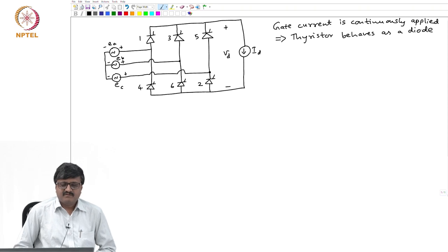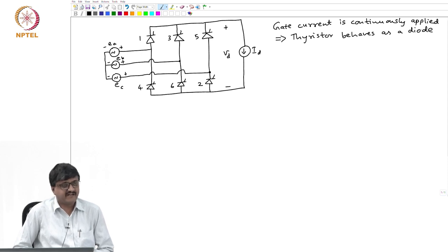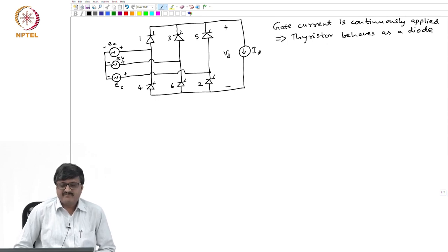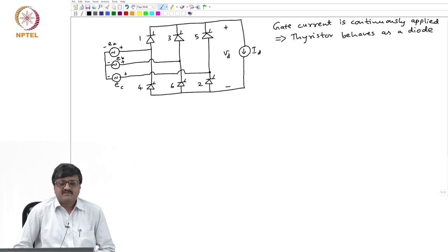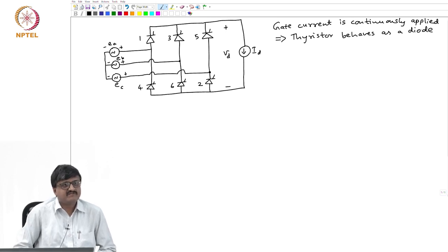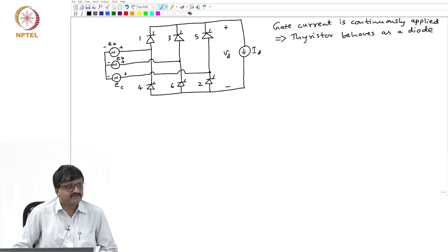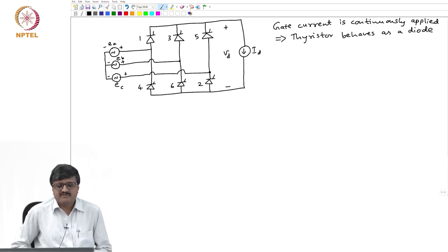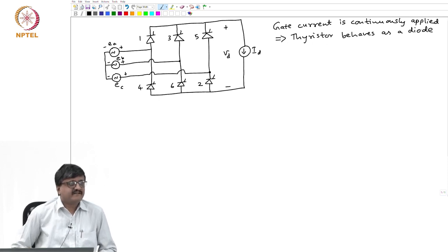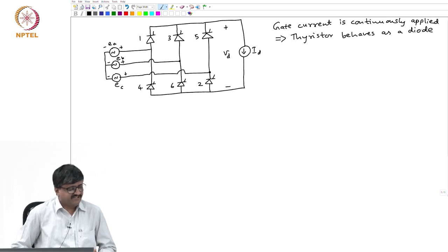The question is: in any commutation group 1, 3, 5 or 4, 6, 2, which is the thyristor valve that conducts? If I take commutation group 1, 3, 5, the cathodes of all these thyristor valves are at the same potential, so the one that conducts is the one with the highest anode potential. Similarly, for the lower commutation group 4, 6, 2, the anodes are at the same potential, so the one that conducts is the one with the least cathode potential.